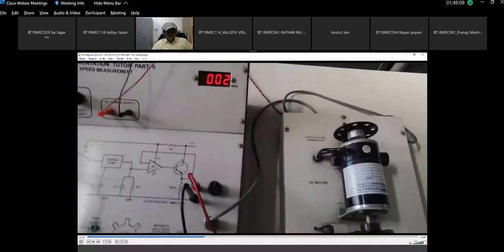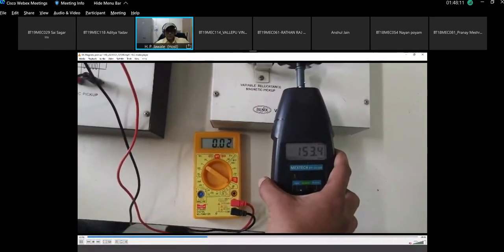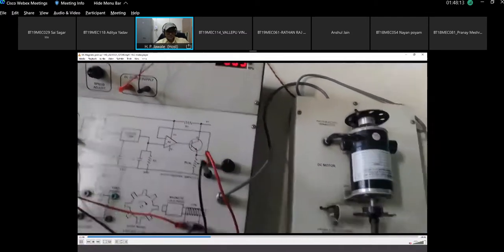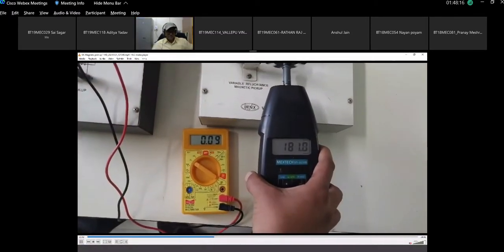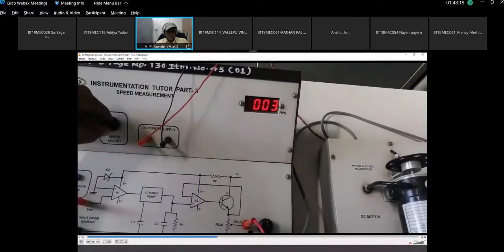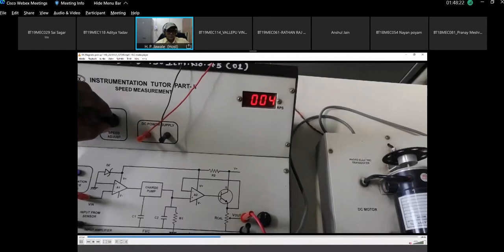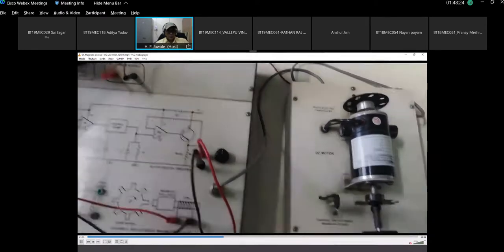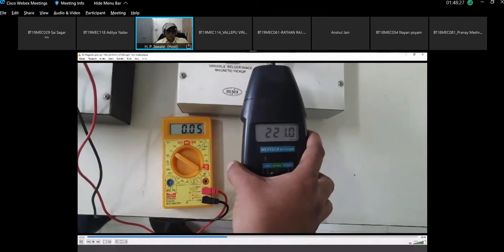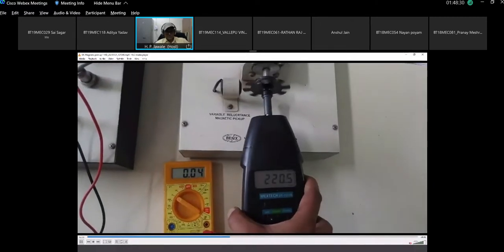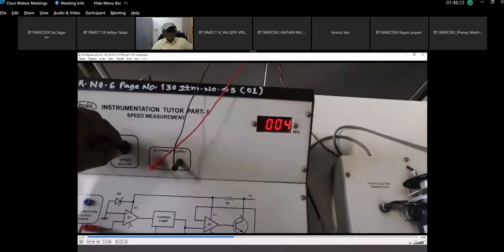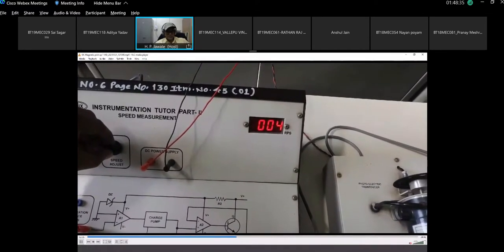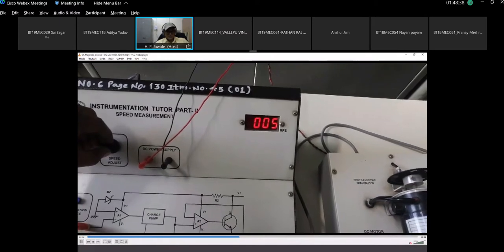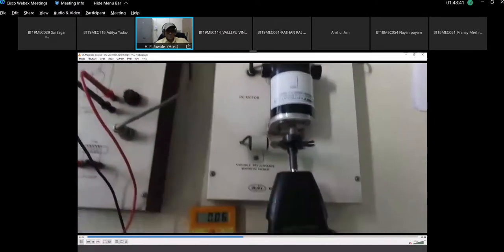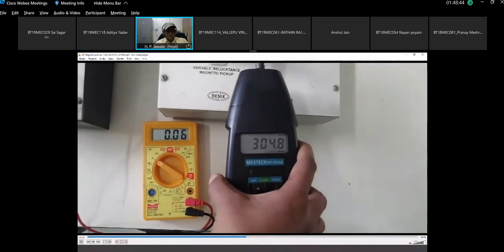For 2 RPS, that is around 120, it should have shown. It is showing 153. 3 RPS, 180 here and 0.3 volt. And I am increasing again. 4 RPS should be 240. It's 221 showing. Voltage reading 0.05. Speed is increased to 5 RPS. It should be 300, but showing 304, 306 something, 0.06 volt.